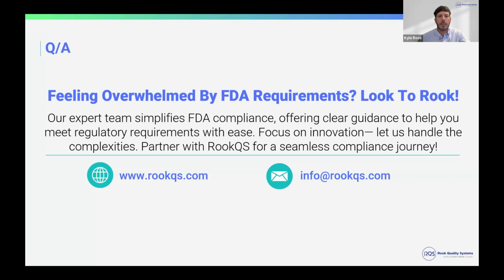It's another question from Sarah Vujovic. Is the FDA biocompatibility assessment guidance to be used as a direction for required testing, but not a replacement for the 10993 testing? So this is very similar to, FDA has a guidance for biocompatibility testing for high-level 10993, not just chemical analysis. So these are designed to work together. With FDA guidance, it's typically things that they want you to look at and focus on specifically that might be in addition to the 10993 standards, and that's why they've created the guidance.